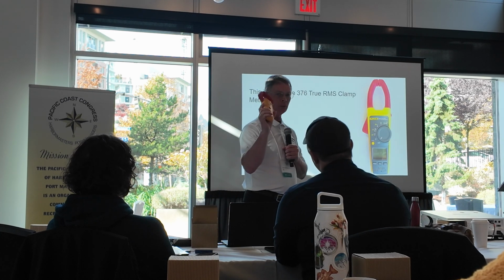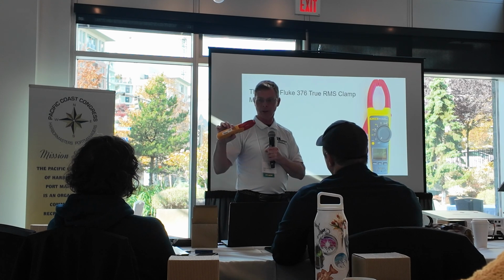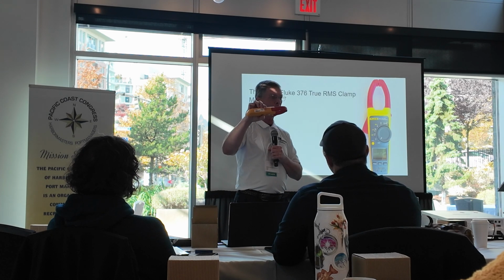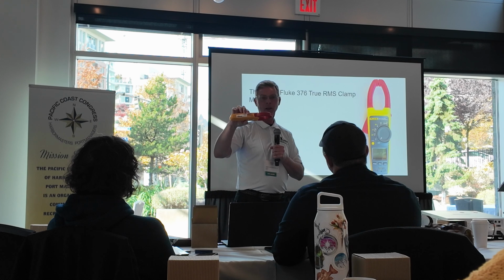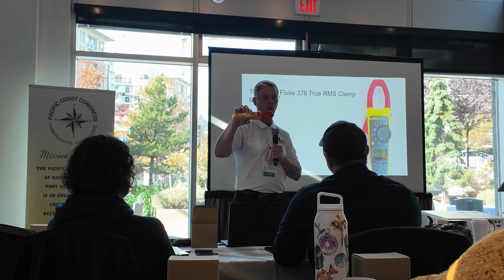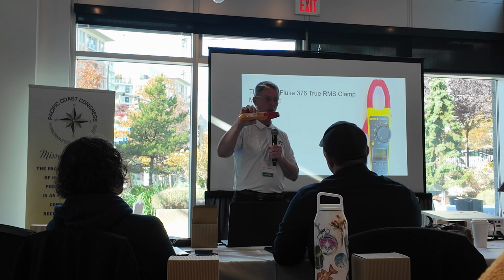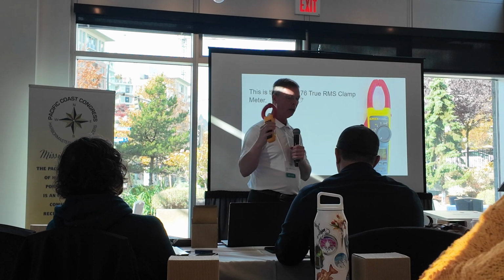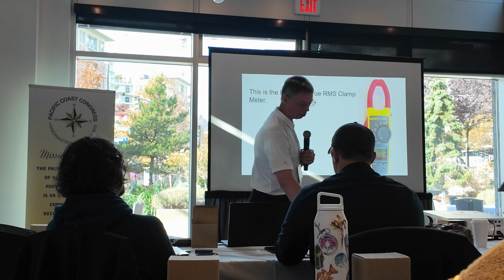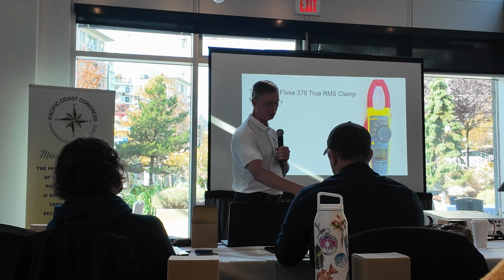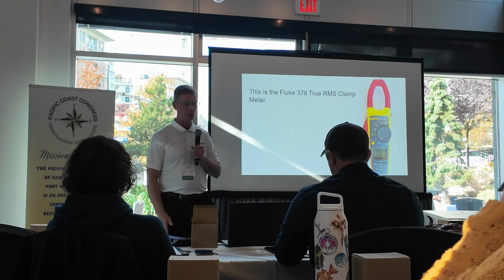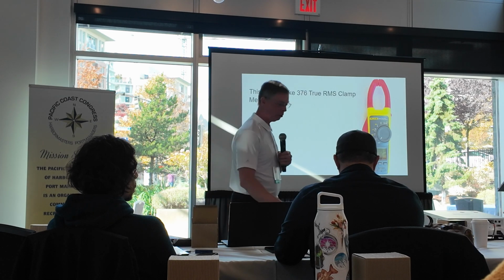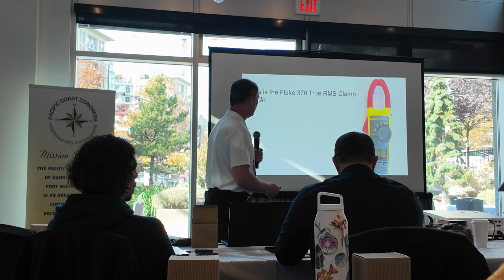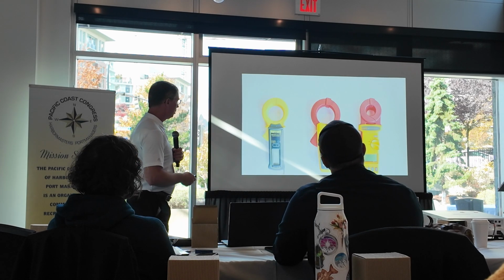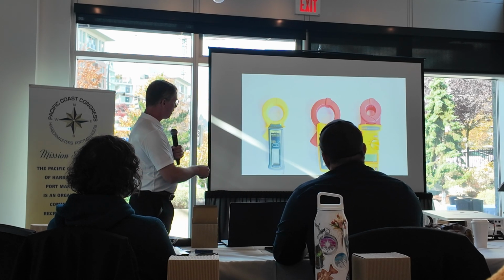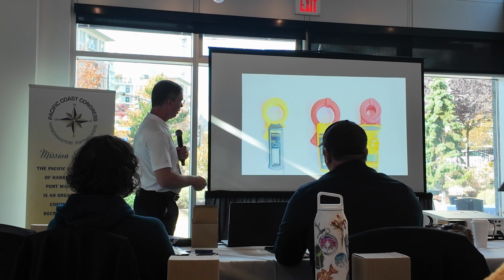So that's my go-to meter, and it's actually calibrated, and it's, a technical term, dead nuts accurate. At 30 milliamps, it reads 30.000 milliamps. At 100 milliamps, it's 100.000 milliamps. And I keep it calibrated because of my expert witness work as well as the commissioning that I do. That's the same meter I use when I do all of the commissioning for all the marinas that I do as well. But they're not all created equal, and I have that meter, that one, and this one.